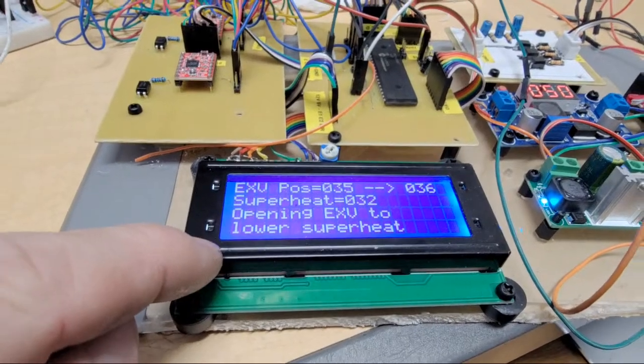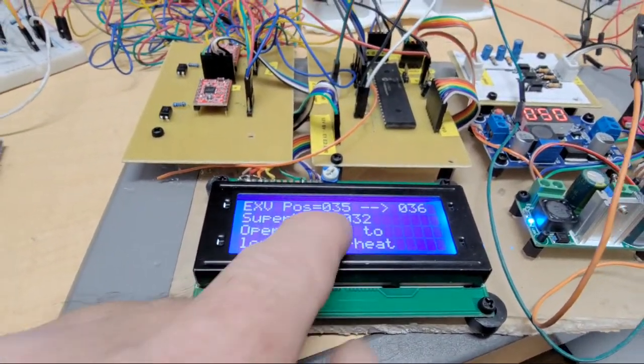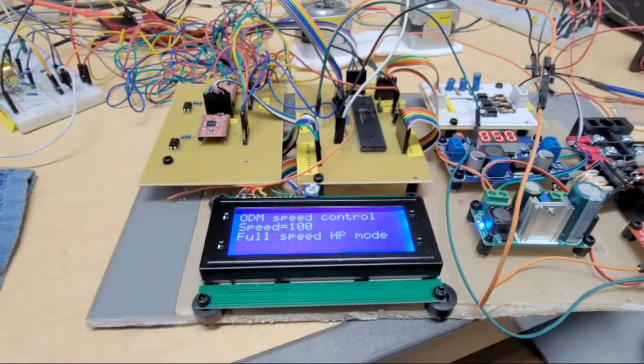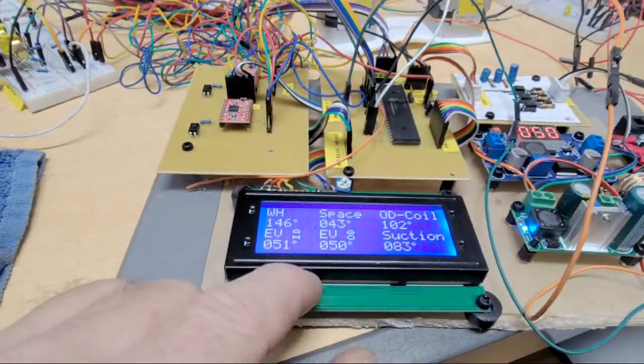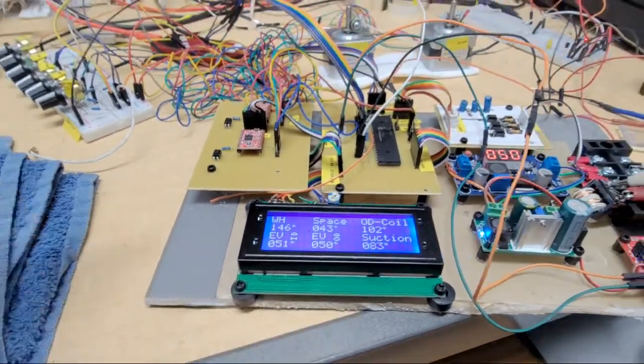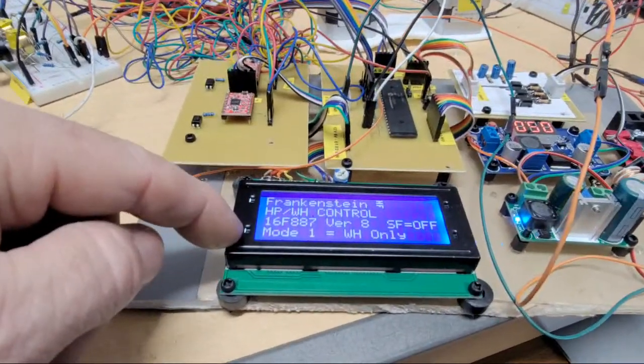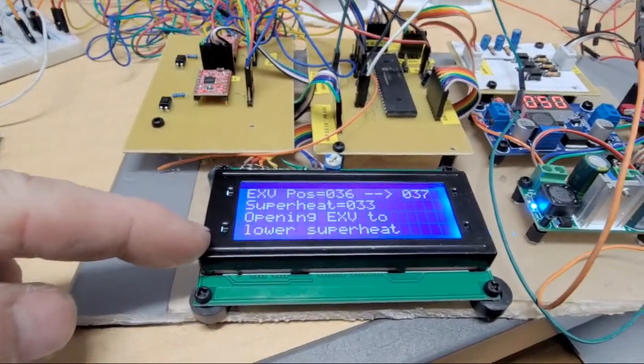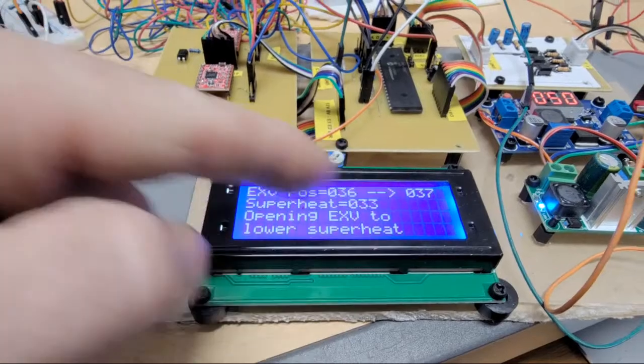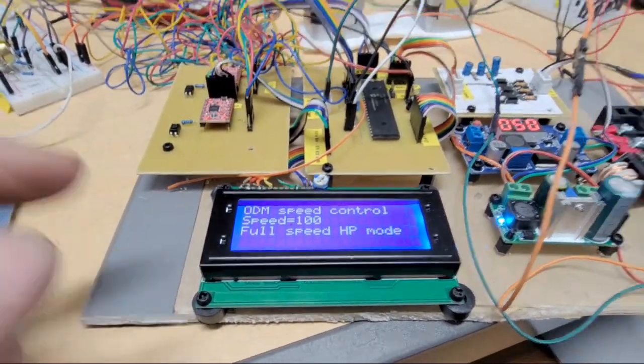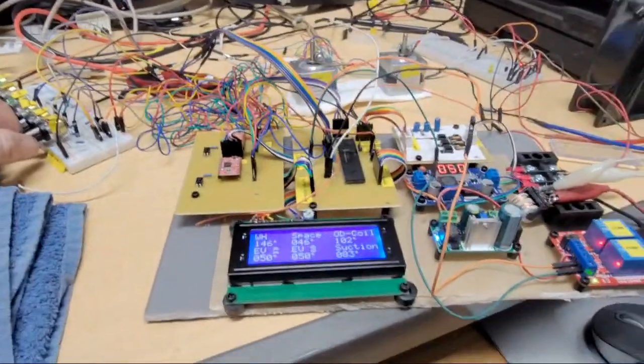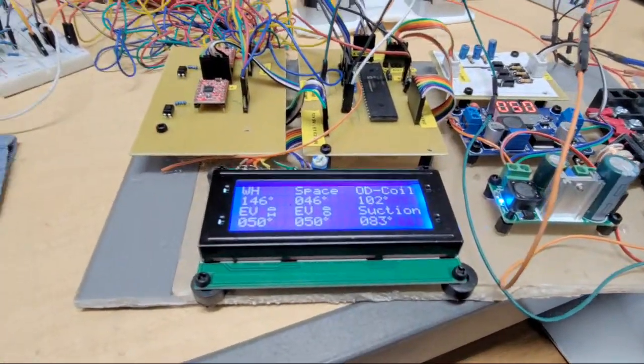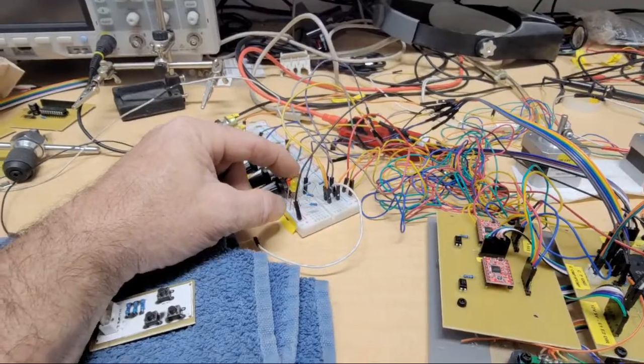So here in a second, all right, now it's opening. See, now it's going to start calibrating. So it's just opened from 35 to 36, the position. And then it reached, and I just have it going through all these different things. Most of this is just for me to troubleshoot and look. I don't even have to have this, but I think it's cool. So now it opened from 36 to 37, and it's going to keep doing that until it gets no more than 12 degrees superheat. And if it went below 10 degrees superheat, it would start closing the valve. So I just have these simulating my thermistors.